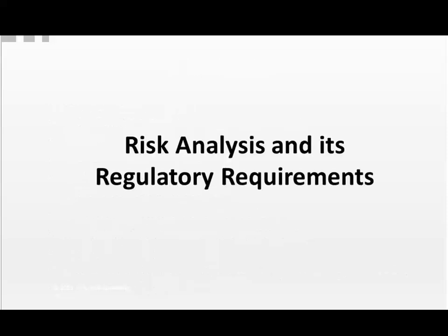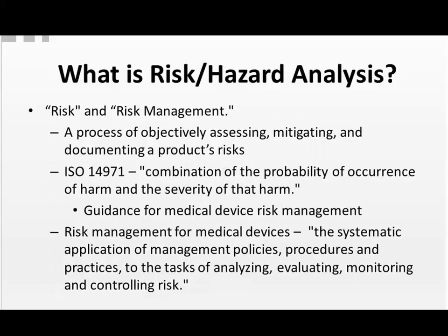Now, let's begin by defining some key terms. Risk analysis, which is a part of risk management, is a structured tool for the evaluation of potential problems which could be encountered using a medical device. It's a process of objectively assessing, mitigating, and documenting a product's risks.